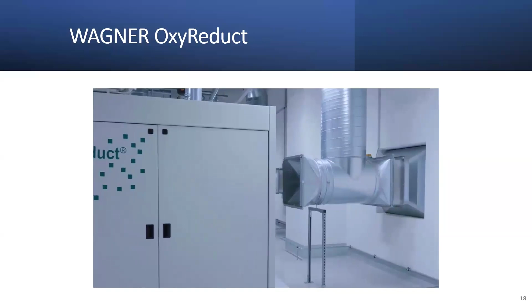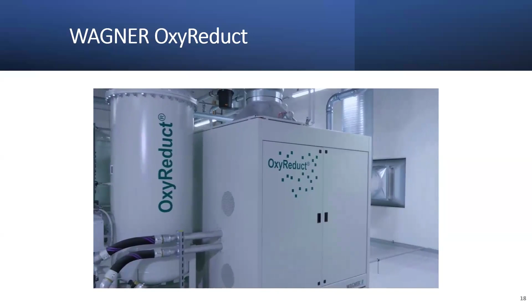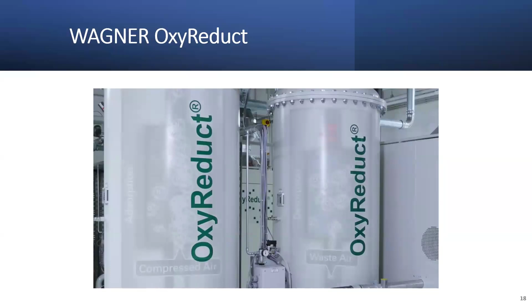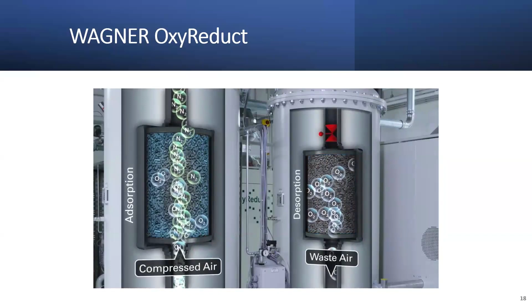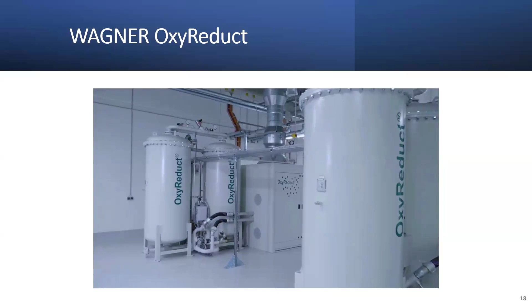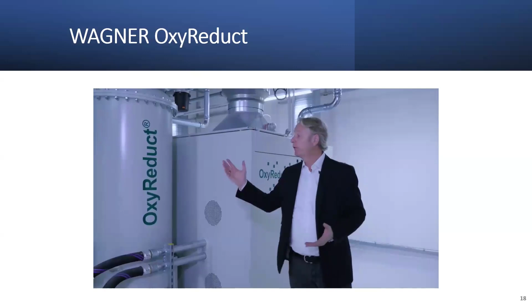The required nitrogen is extracted from the ambient air on site in an energy-efficient manner by our OxyReduct system. It generates nitrogen by separating oxygen and nitrogen with the help of active carbon. While the active carbon binds the oxygen of the compressed air in the CMS tanks, the nitrogen is released into the protected area. The OxyReduct system's performance can be adjusted flexibly. It saves on installation space and eliminates the need to keep a supply of extinguishing agents on hand.